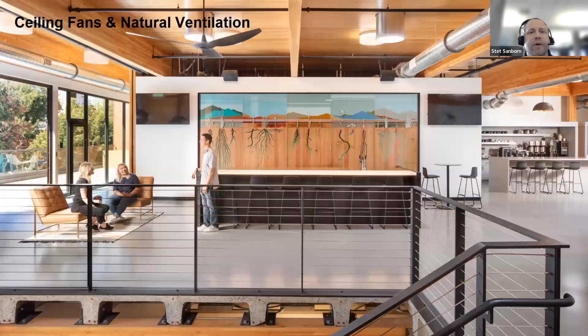On the next slide, I do want to highlight one of the other key things that allowed us to right-size the heat pump and reduce its overall size. The first one was we added ceiling fans, which increased air movement across the skin of the body and allows us to set the cooling set point up about 3 degrees. For this project, the cooling set point is 78 degrees instead of 75 like a typical office building, because that additional air movement provides a sense of comfort. Adding ceiling fans plus the change in the set point allowed us to reduce the size of the heat pump to meet that peak summertime cooling load.